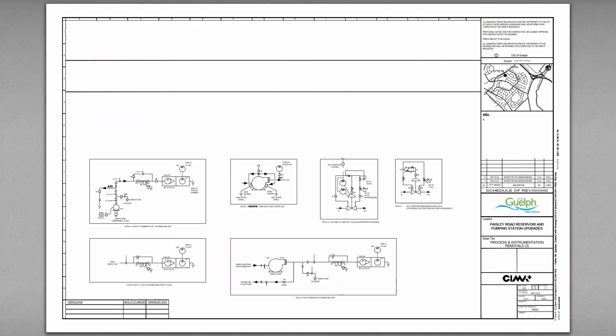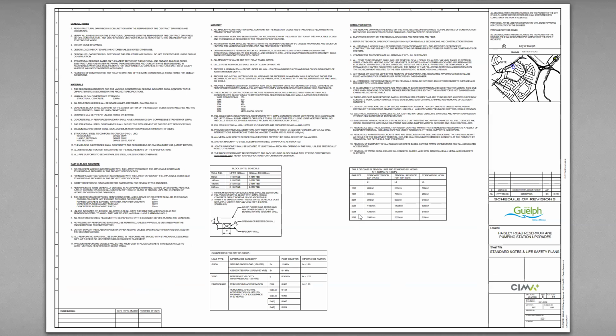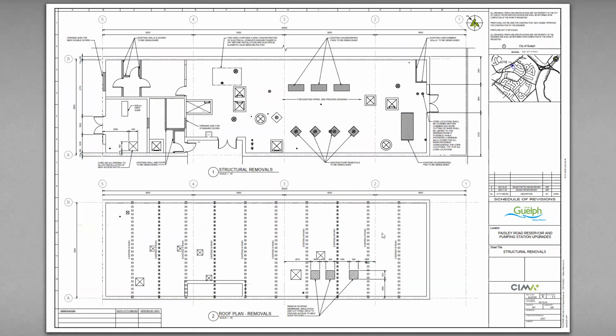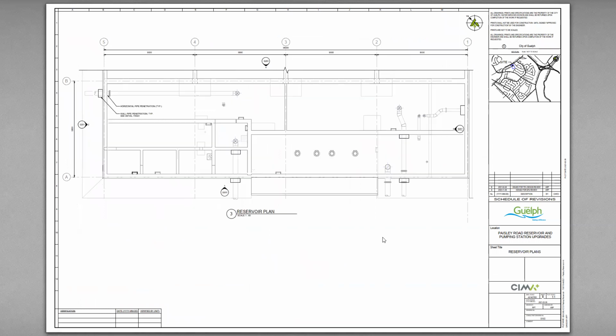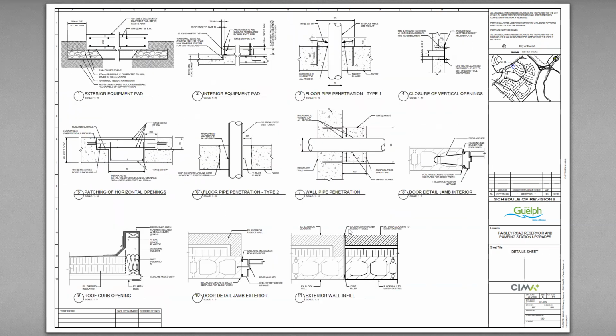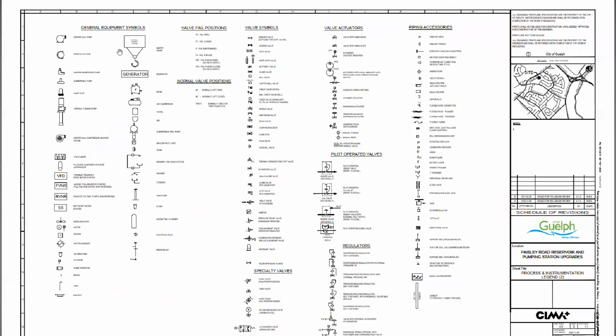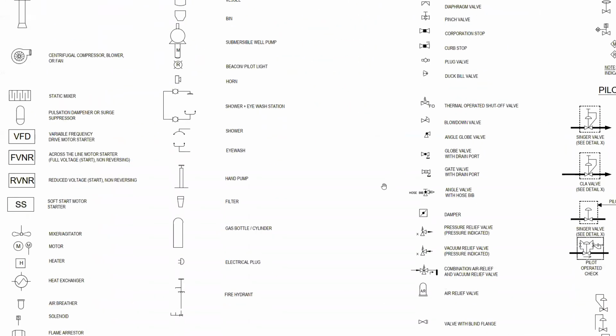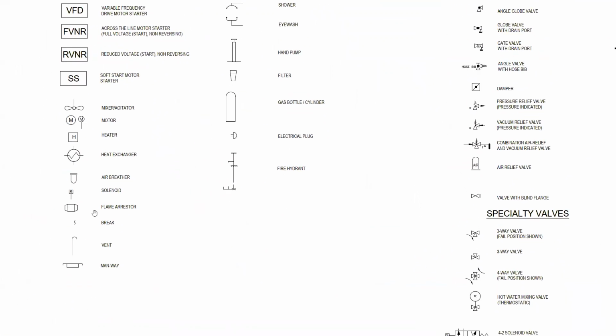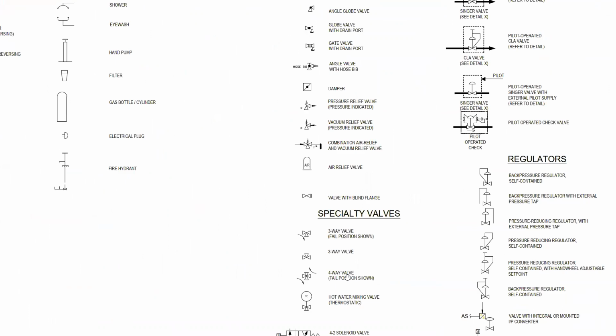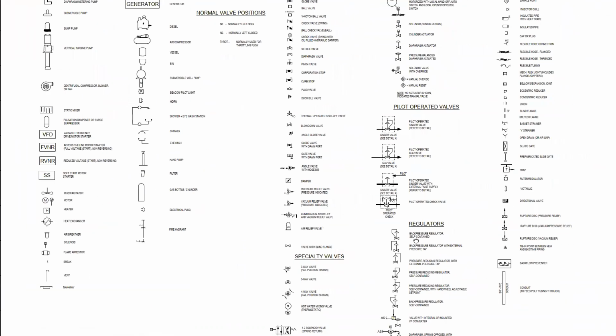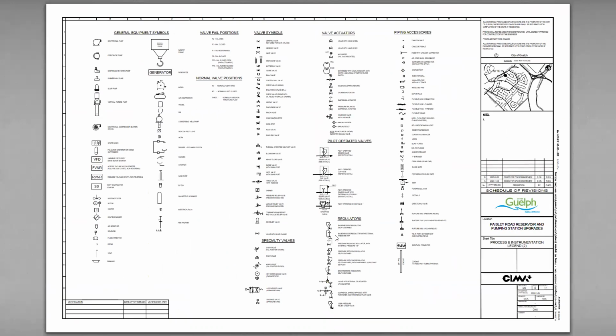Part of my job with this and the engineer's job is to look through and make sure that we catch all the details, that the detail that tells them how big the pumps we need are there, so that they can potentially size all the electrical protection equipment properly and bid on it. Here's construction information on it. Here's their legend for their mechanical. So we've got VFDs, mixers, vacuum relief valves, four-way valves, solenoid valves. You can get the picture, I'm sure.